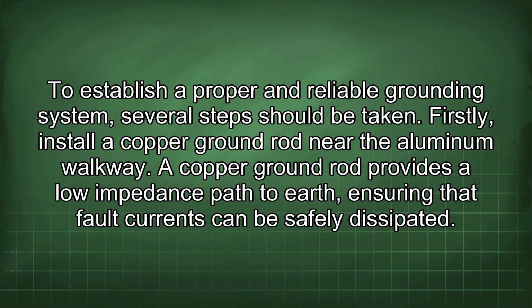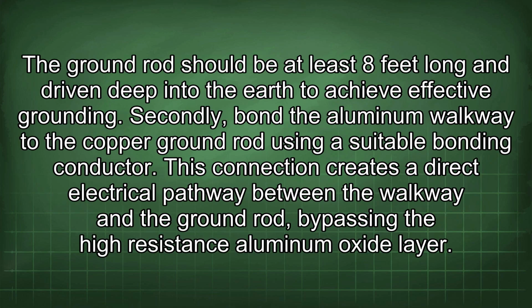Firstly, install a copper ground rod near the aluminum walkway. A copper ground rod provides a low impedance path to earth, ensuring that fault currents can be safely dissipated. The ground rod should be at least 8 feet long and driven deep into the earth to achieve effective grounding.